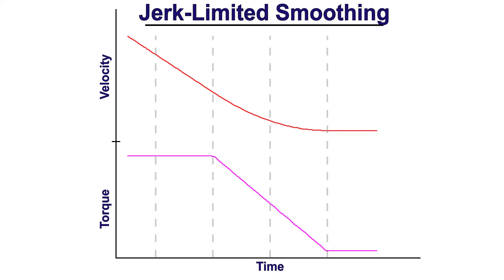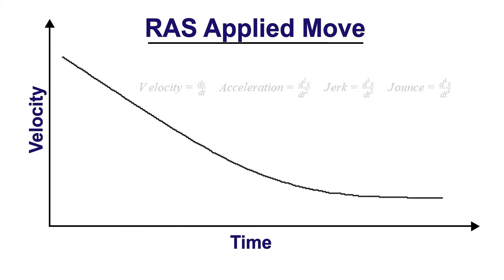That's where the RAS comes into play. A jerk-limited and jerk-derivative-limited profile - where the jerk-limited profile controls the rate of change of acceleration, the RAS controls the rate of change of the rate of change of the acceleration. You're taking it one derivative further, which as you'll see creates an extremely smooth motion profile. I think you'll be pretty shocked to see what the torque actually looks like when the RAS is applied.